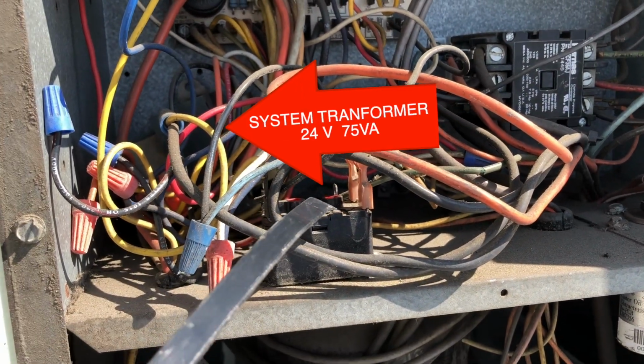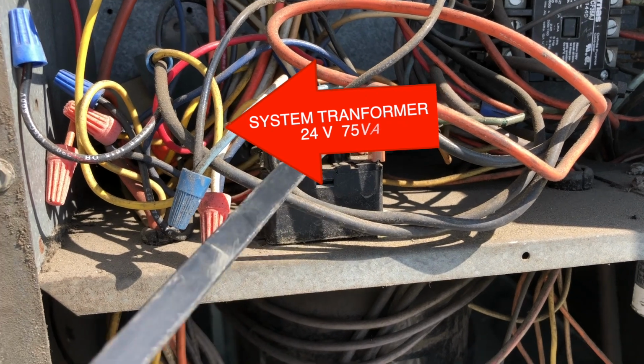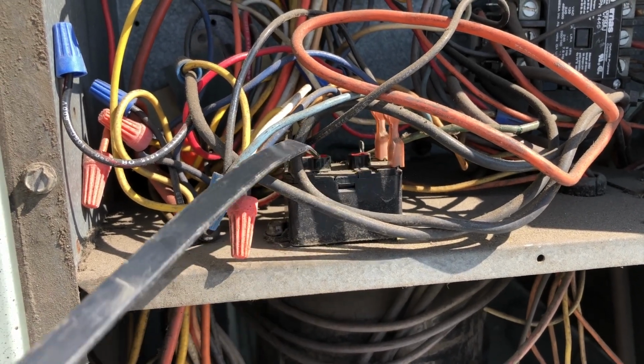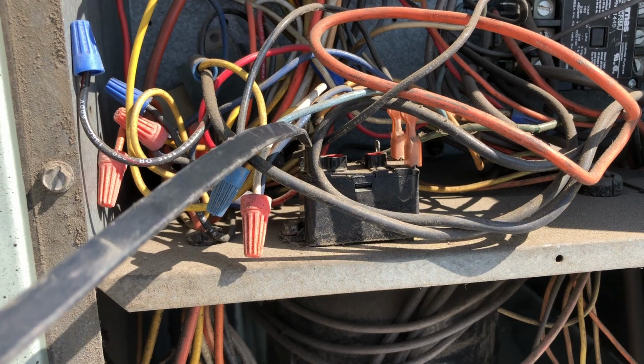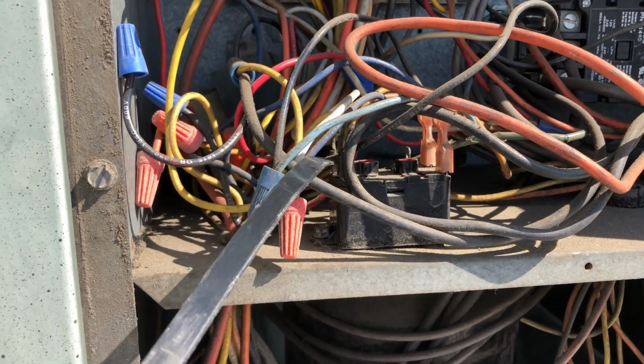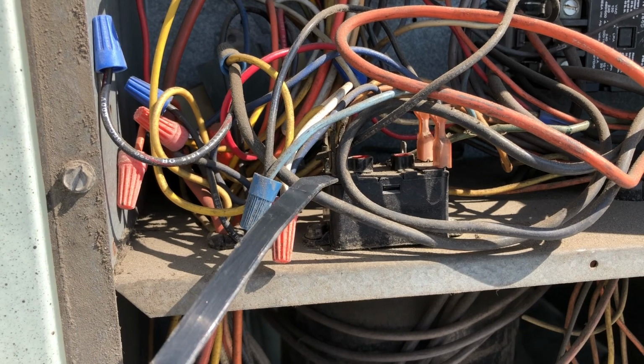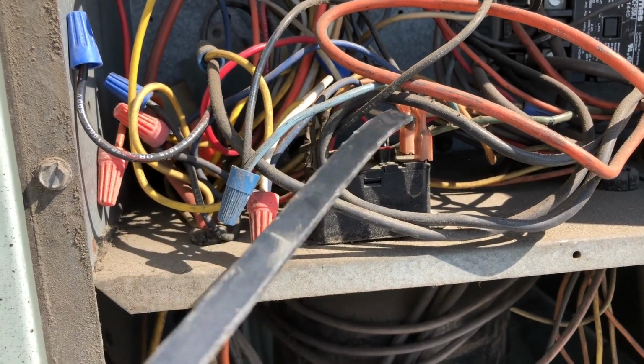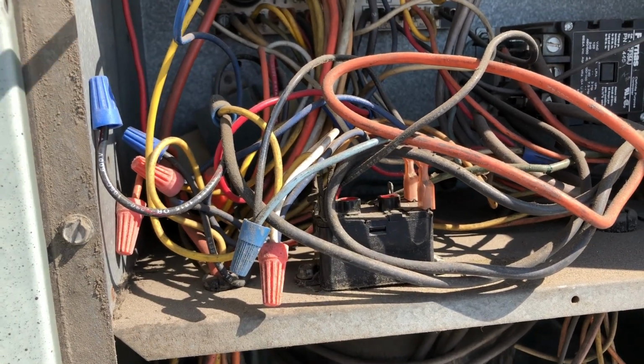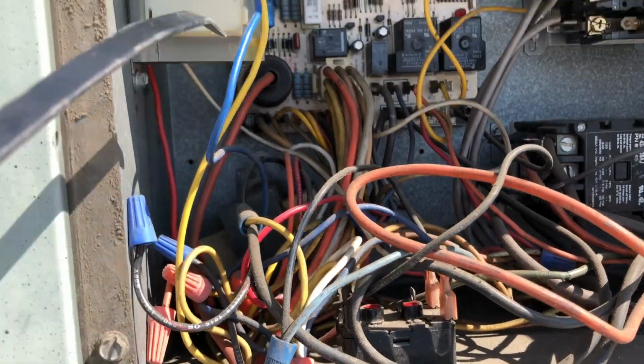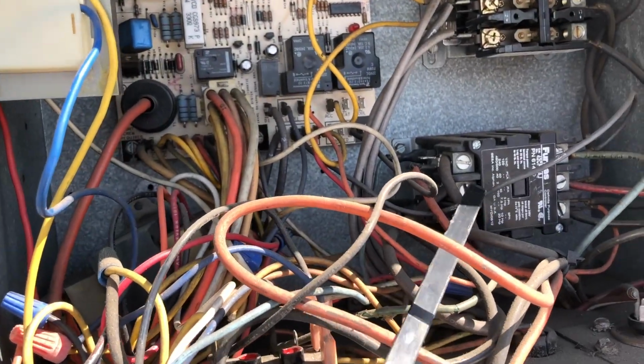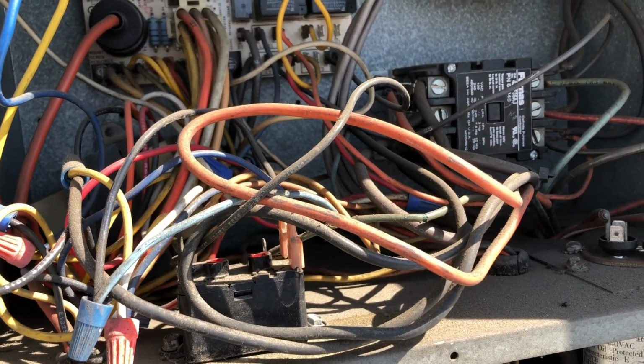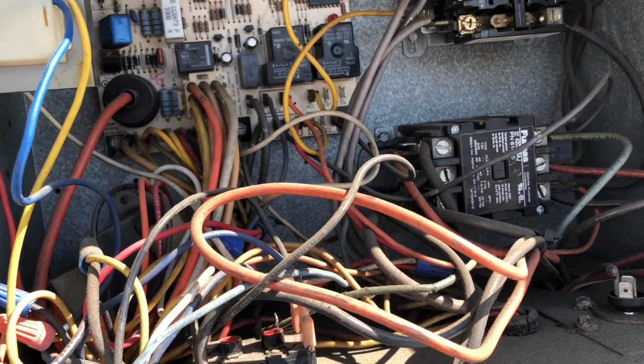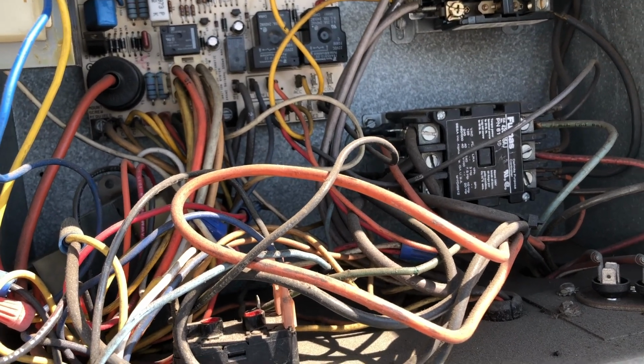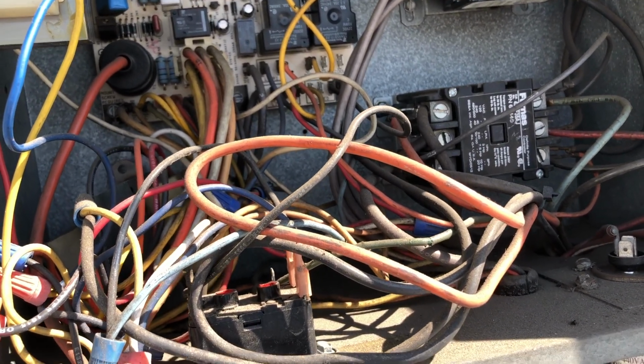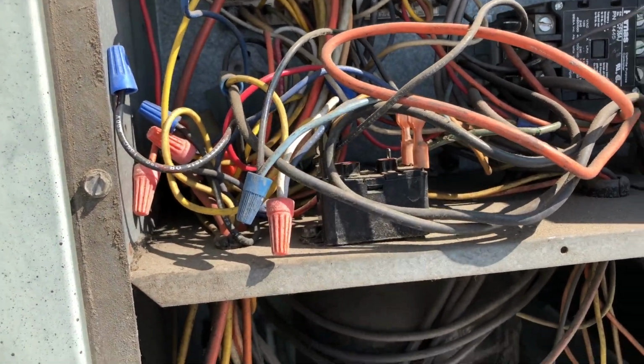So when the relay pulls in from a call from the thermostat, the Y pulls in the relay, the contacts switch over, and it sends 24 volts from the transformer to the contactor. So I got full power, and it's been this way for 20 years. I haven't been here in a long time, probably 10 years. So that was an old school low voltage hack.